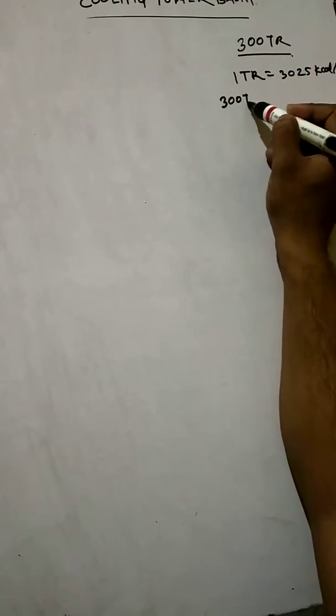Dear friends, today we are going to see the cooling tower basin — how to design the cooling tower basin. Suppose your cooling tower capacity is 300 TR. 1 TR is equal to 3025 kcal per hour, so 300 TR is equal to 907,500 kcal per hour.